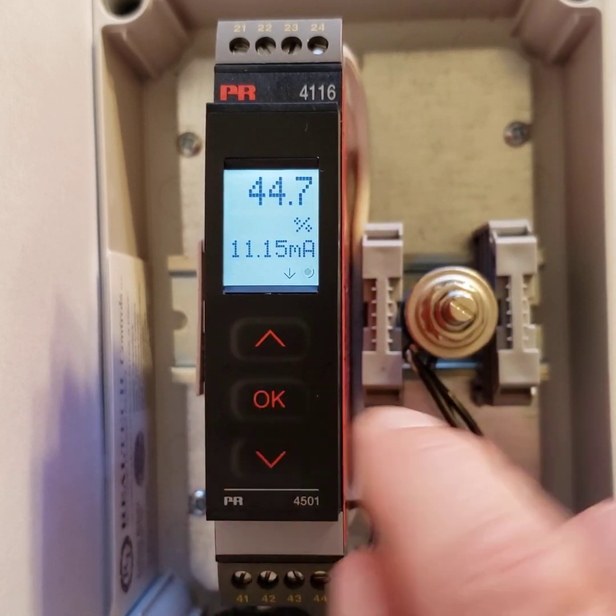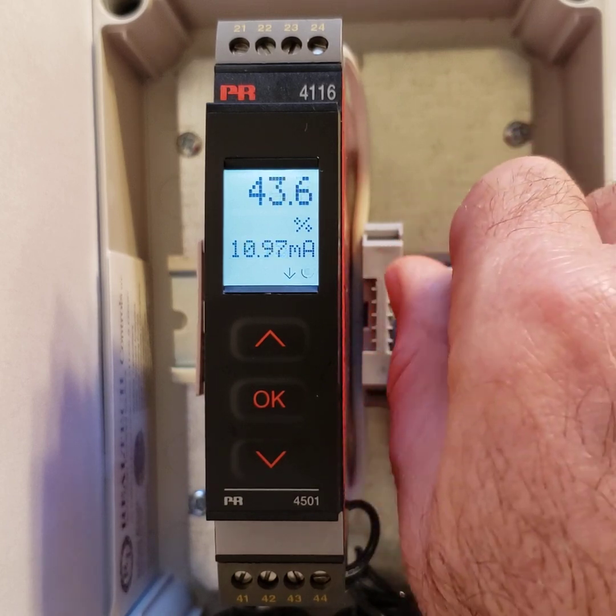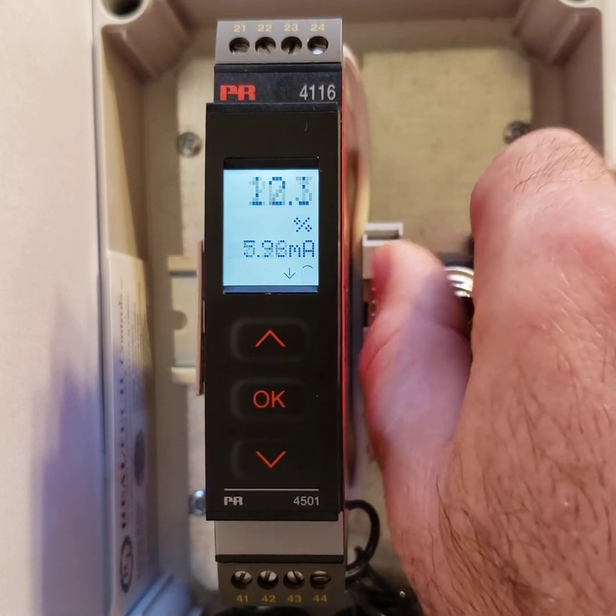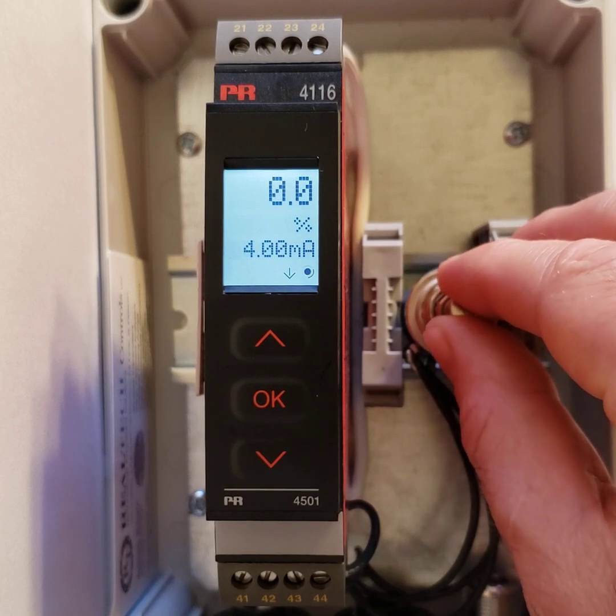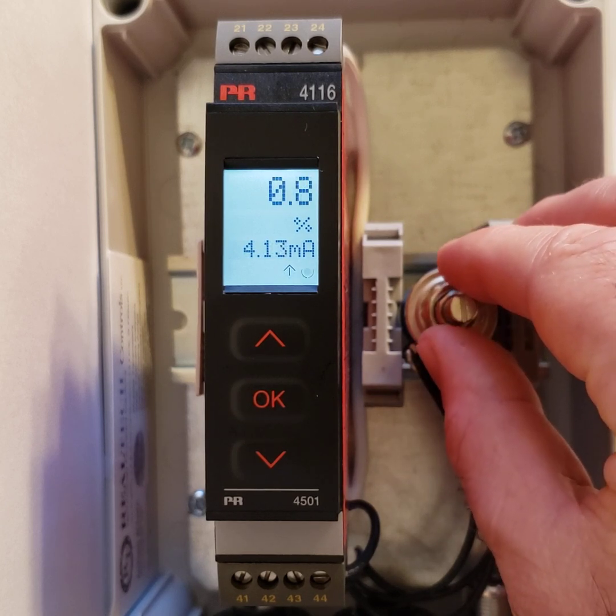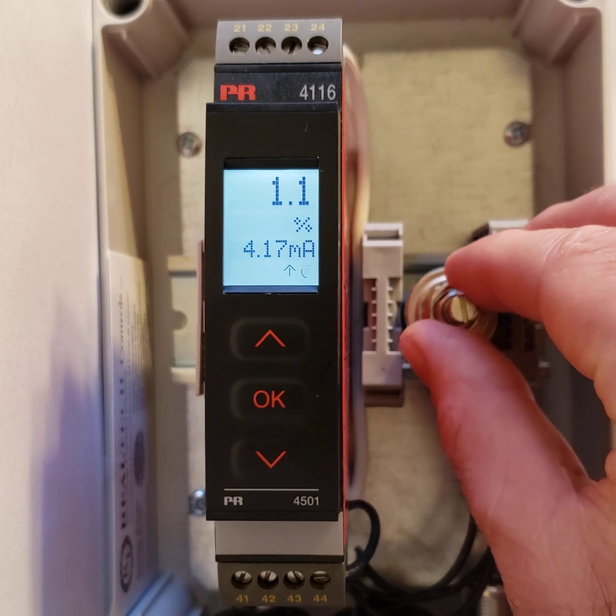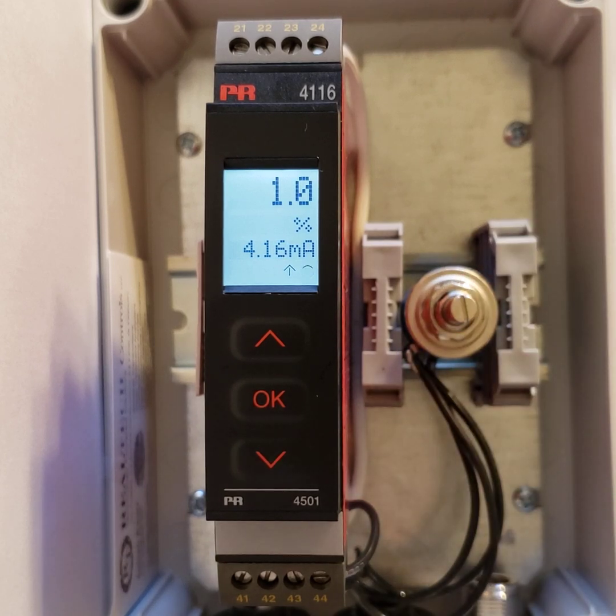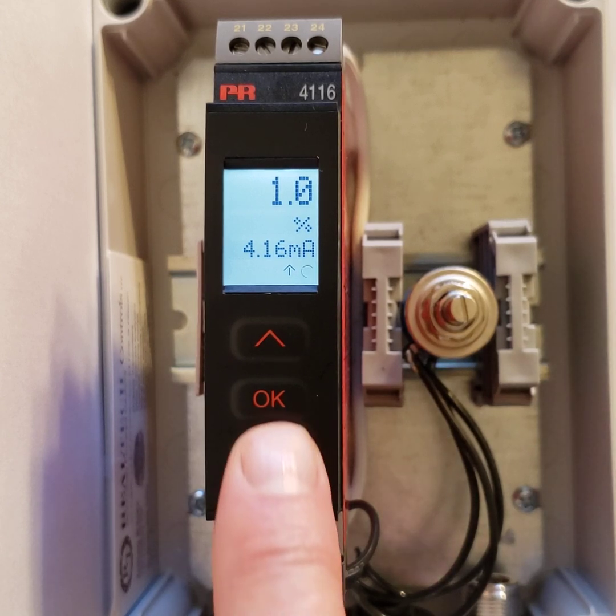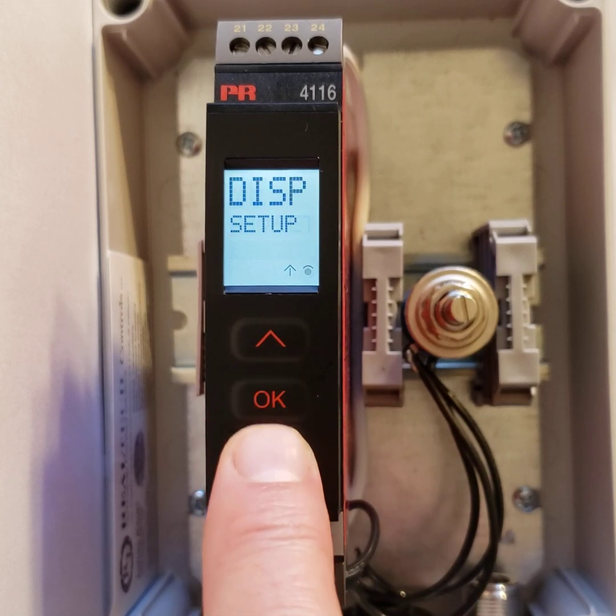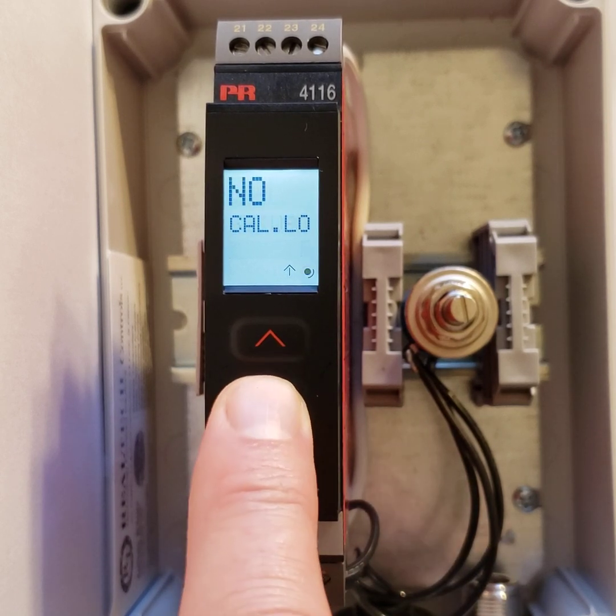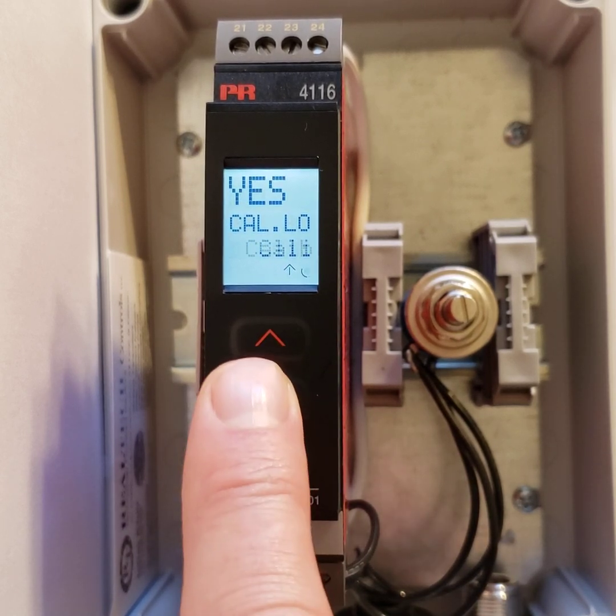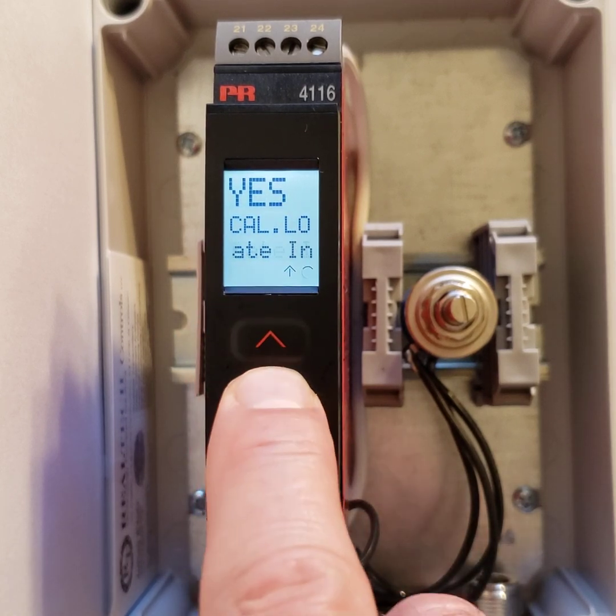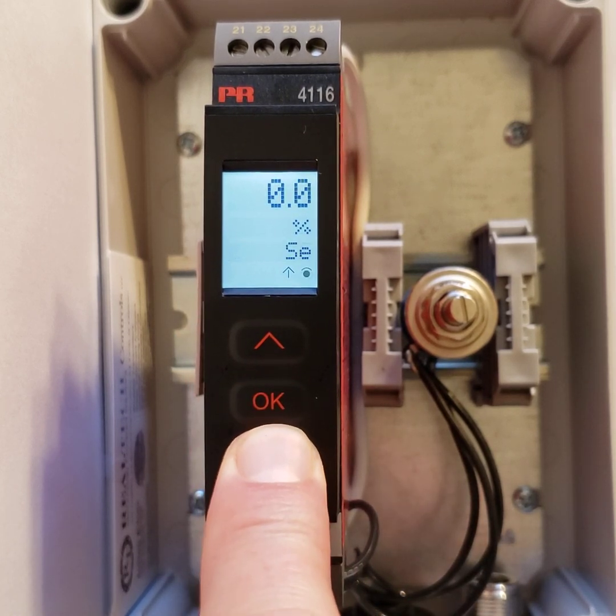The next item is calibration. And what I'm going to do is set the potentiometer to say 1%. Say for instance, you've got a little bit more water in a tank and it's 1%, but your tank is actually at 0, but your transmitter for some reason is showing higher, and you want to calibrate that to exactly 4. In Cal, you set up your low calibration. It says calibrate the low. You choose yes, and I want to select that to 0.